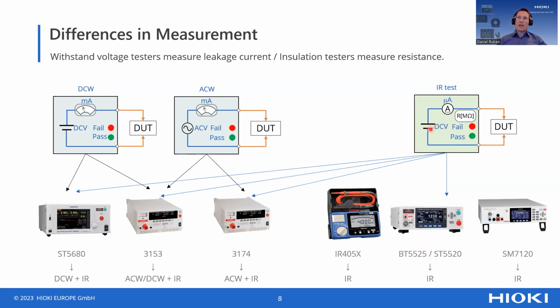Here we will apply a very stable DC voltage to the DUT because we know the very stable DC voltage, and we have a very, very high resolution sensing of the current. We are then able to calculate the resistance value. So here it's about the insulation resistance, which is interesting for that. One point for the portfolio, ST5680 is an addition to our existing portfolio, specifically targeting the battery industry.